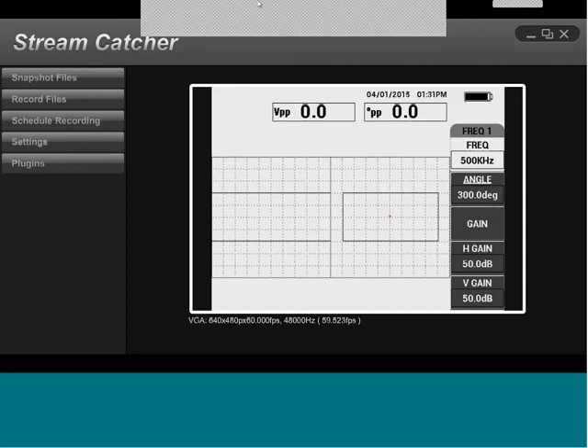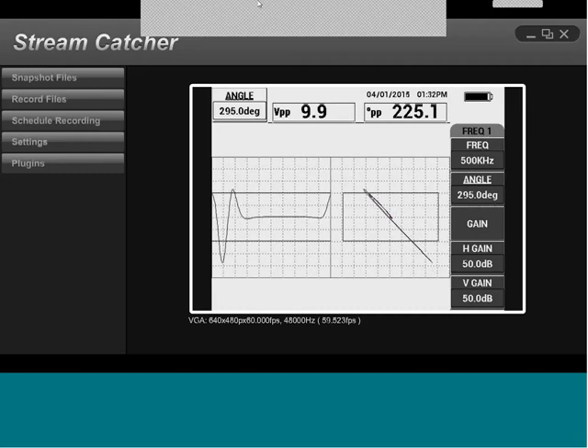So let's see that. Now I have an aluminum standard, okay, so I'm going to null the probe. Now I just start the scanner. You might actually hear it rotating. And let's do the step. Well, if application selection was step number 1, let's do step number 2, which is adjusting the liftoff. So right now I'm setting my probe to barely touch or graze the surface, and then I press the angle key and adjust the angle with the knob. So I'm trying to put my liftoff as horizontal as possible, and because the system defaults to figure 6, that means 180 degrees reading.